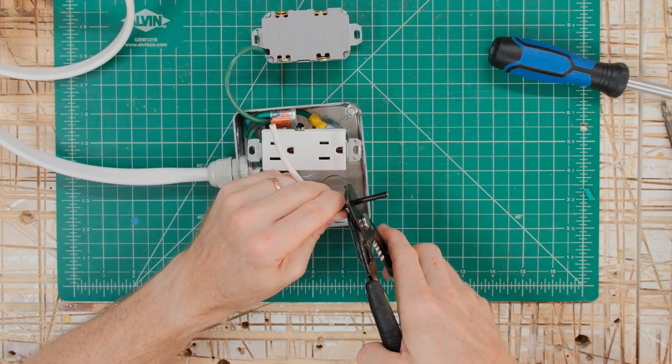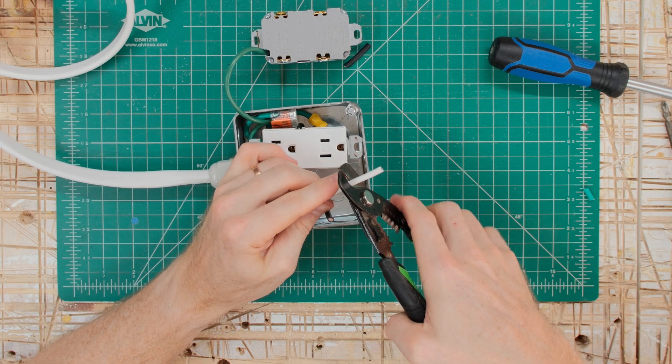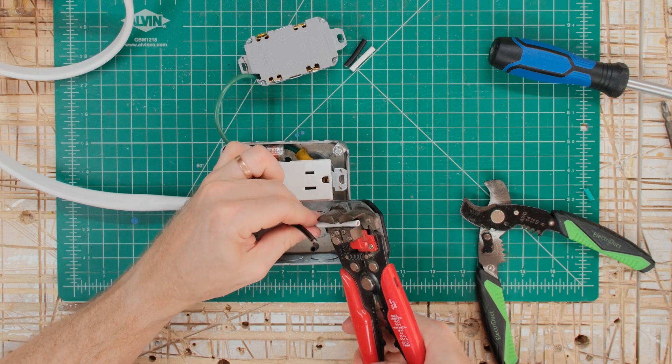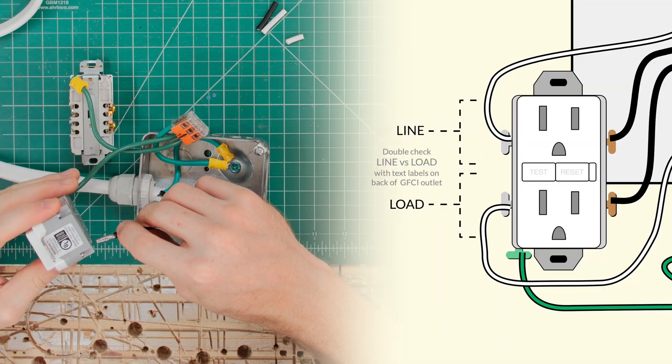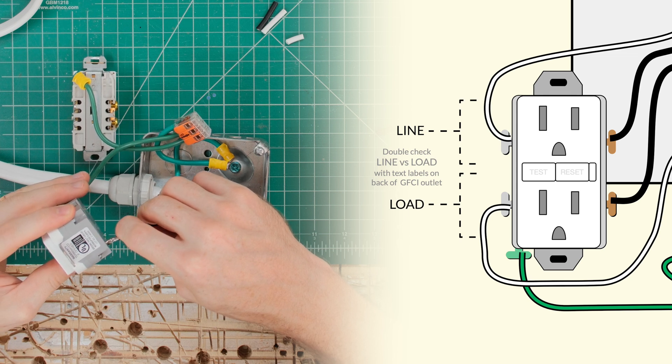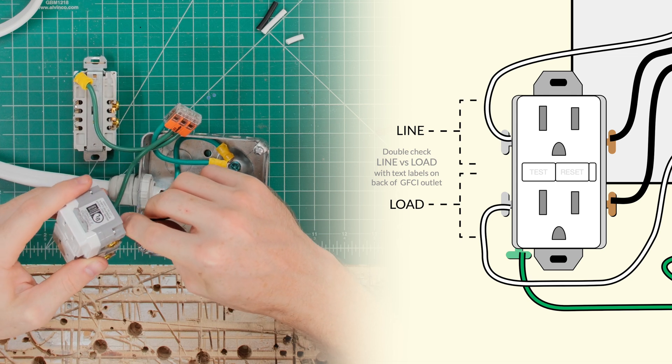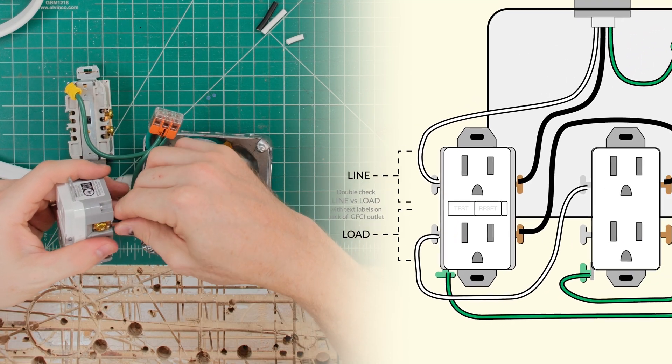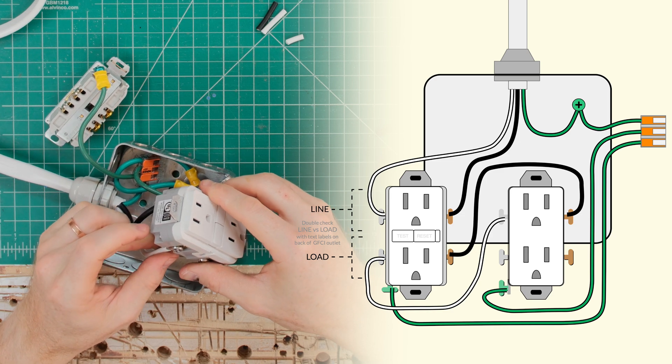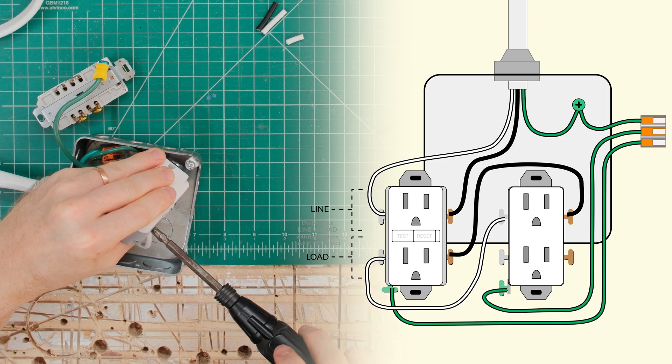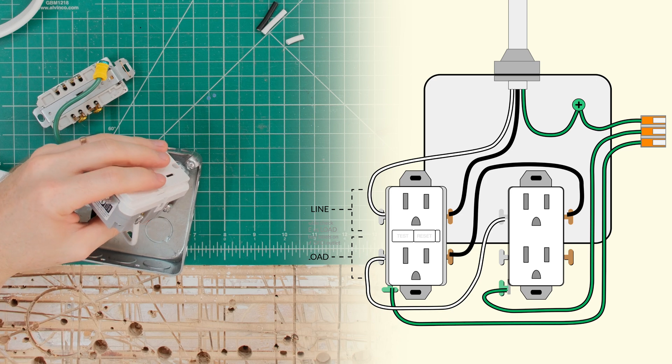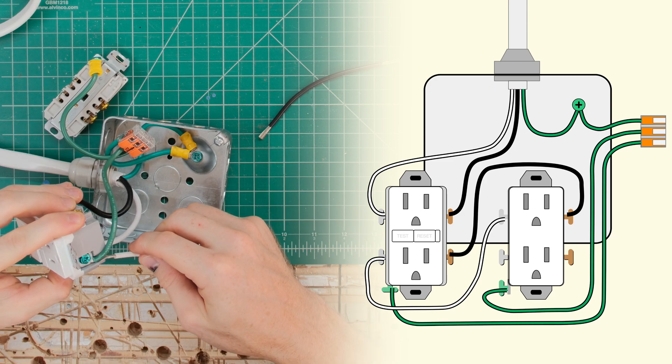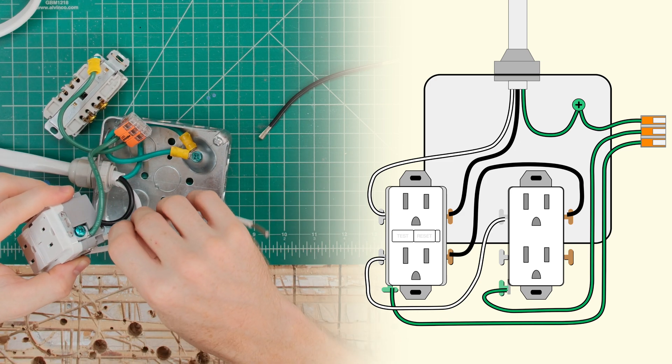Next up I'll connect the hot and neutral wire from the main cable coming into the box to the line side inputs of the GFCI outlet. The GFCI outlet has one set of connections labeled as line and a second set labeled as load. In order for the GFCI protection to work properly and protect the second outlet, you must connect the line versus load correctly. The line side connects to the power source, or the power coming into the box, and the load side connects to the second outlet. The black wire, which is the hot wire, connects to the brass colored screw, and the white neutral wire connects to the silver screw.